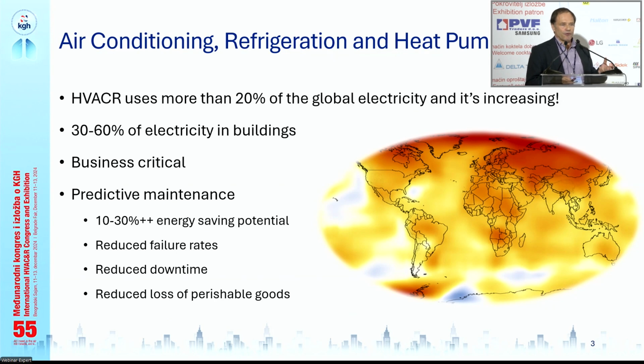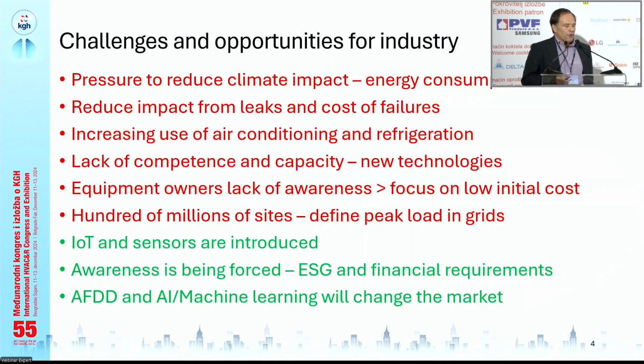So we also know that climate change by itself is increasing the need for air conditioning and refrigeration. We know that the grids are typically straining to supply the capacity at certain hours. So we need to really use our system to reduce the peak loads. Our systems are generally very slow. There's a lot of inertia in a cold store or in a building, so you might not need to run so much at those specific hours.